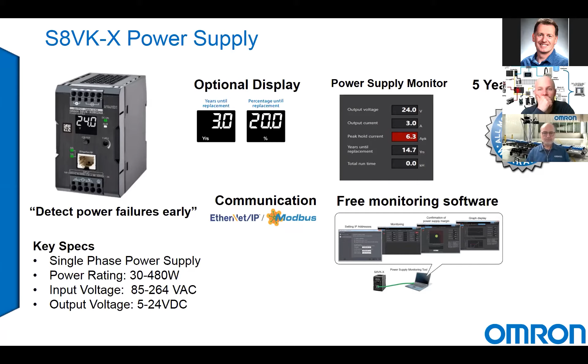So we've introduced power supplies with an Ethernet IP or Modbus TCP connection. By default we use Ethernet IP, which is easier for our controller, so you can monitor your power supply remotely, giving constant 24/7 monitoring. You can predict whether it will need maintenance or replacement soon, because it has a built-in aging system showing how many months or years, or what percent of its service life has been used. It's very user-friendly programming, like a Windows application.